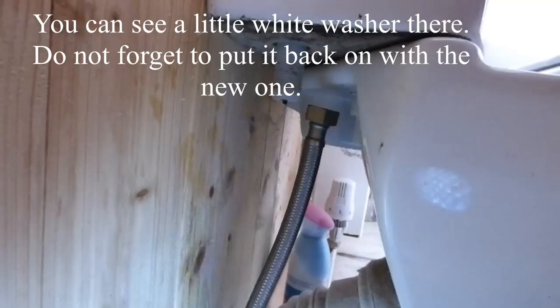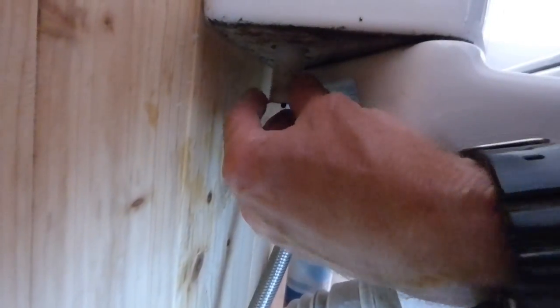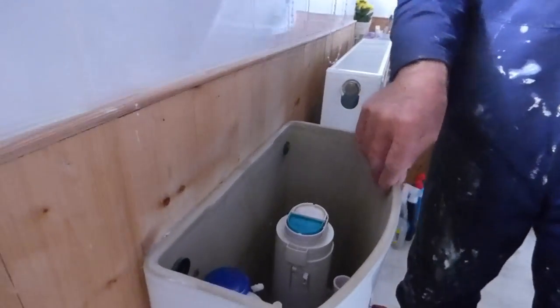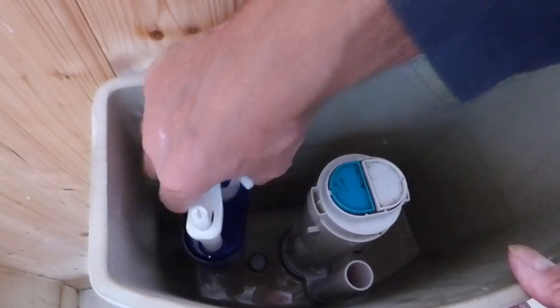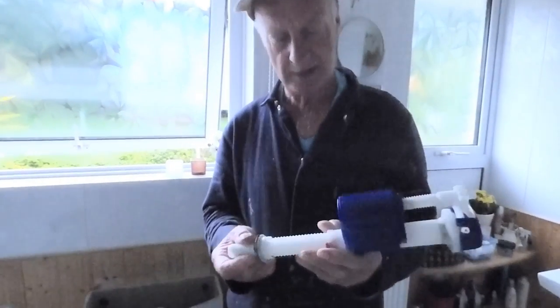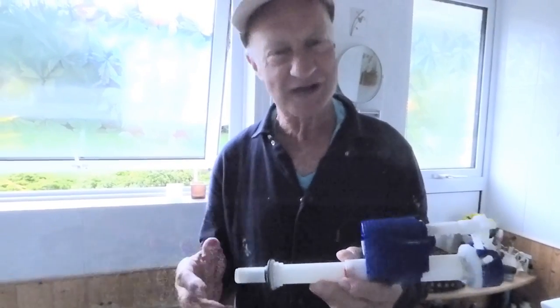Spin it right out — it's gone down behind the back of the panel, they usually do. Once we've got it off we can pull the valve out now. Come to the top and we'll show it coming out. Jan on the camera today. It should just pull out like that, and there we have it — one valve removed.